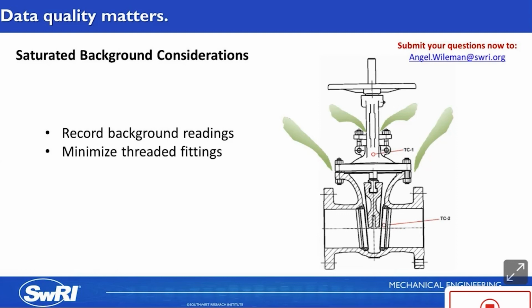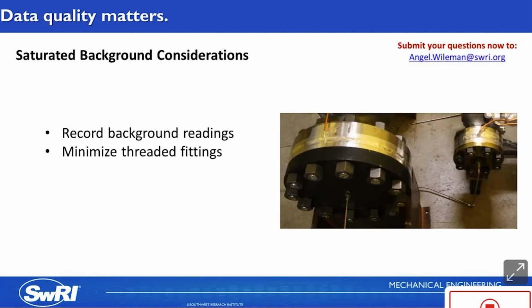One way to help prevent elevated backgrounds is to minimize the number of threaded MPT fittings that you use on your test stand. MPT threads are the worst for leaks, especially testing with gases. So one spot that we noticed frequent leaks from was actually the end flanges that are connected directly to the valve being qualified. We switched from drilling and tapping the flanges and using MPT threads to drilling a straight hole through the blind flange and then welding a tube fitting to it, and this helped tremendously.